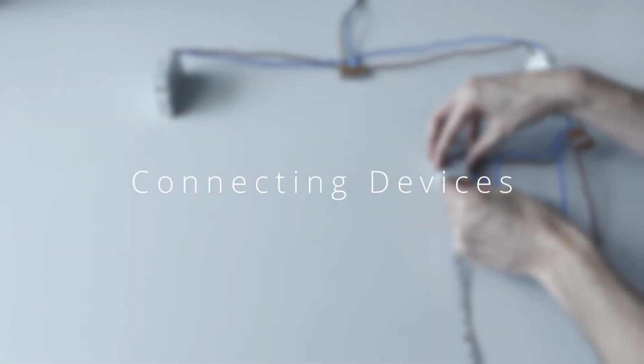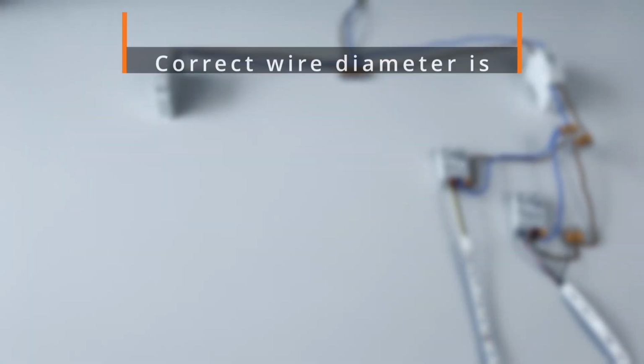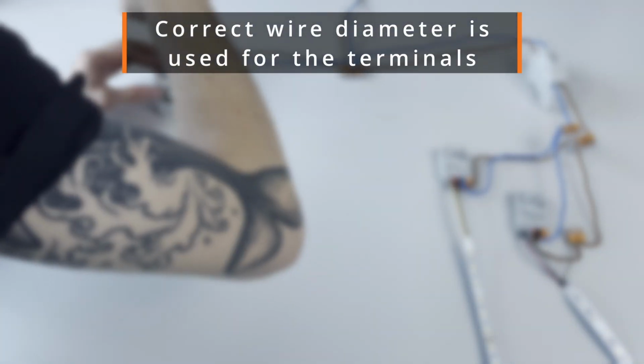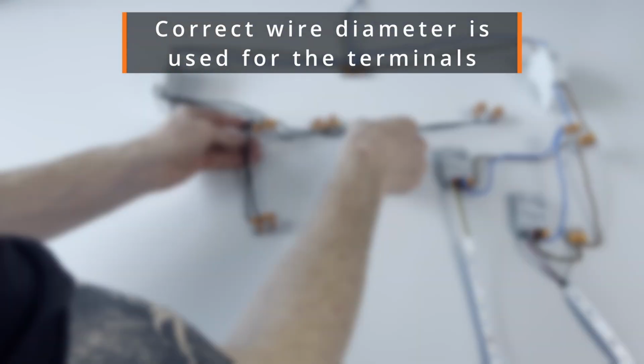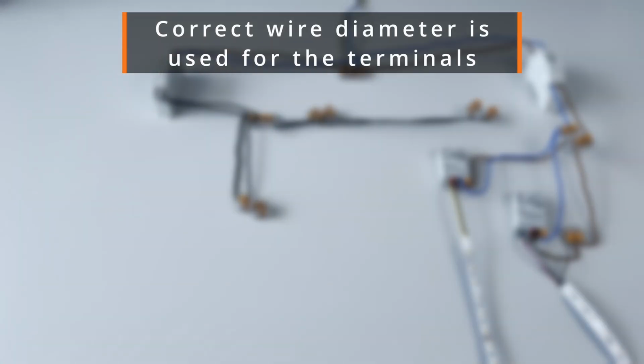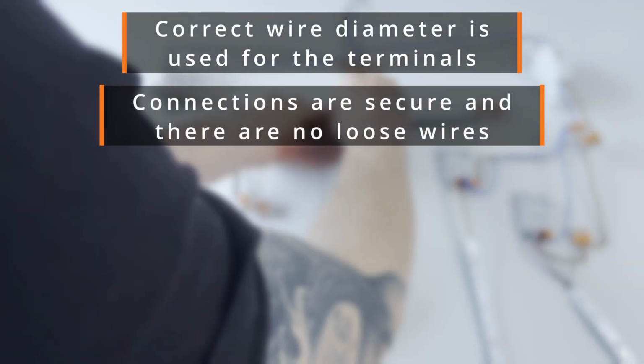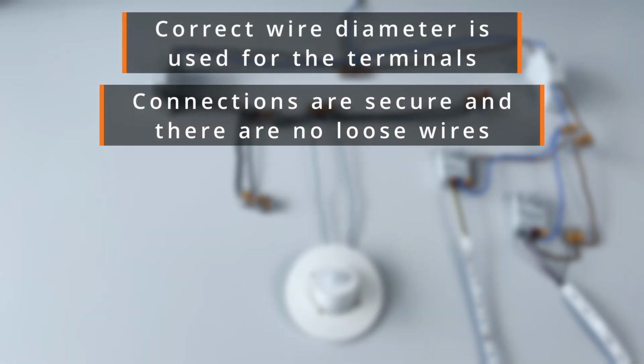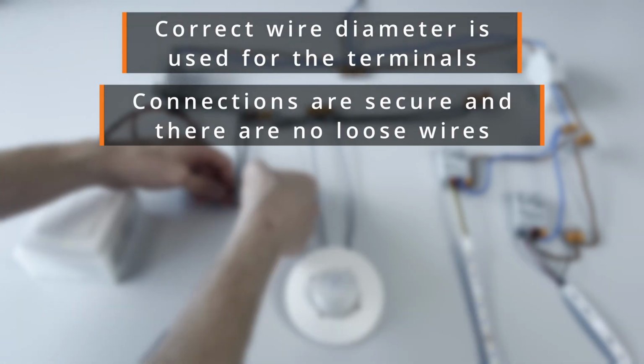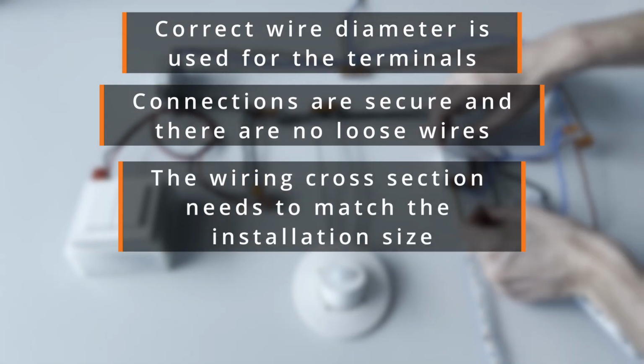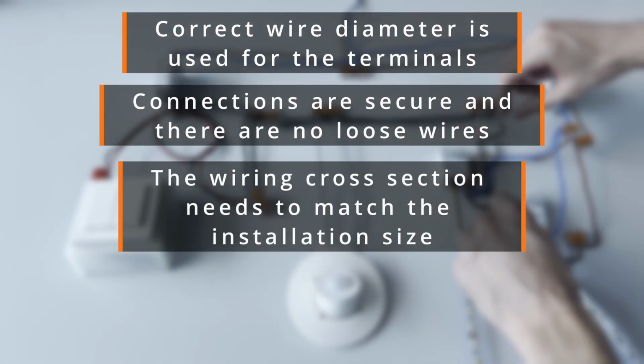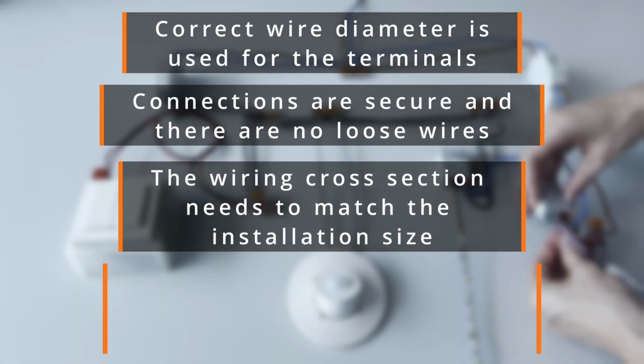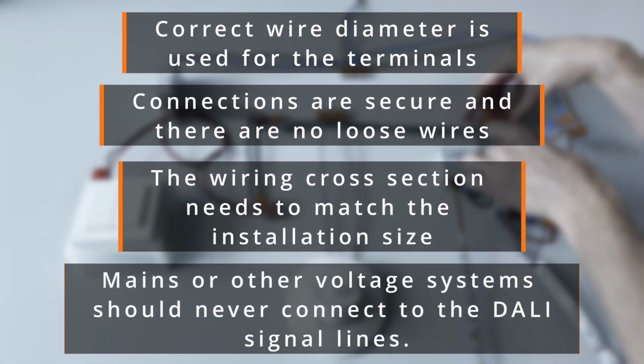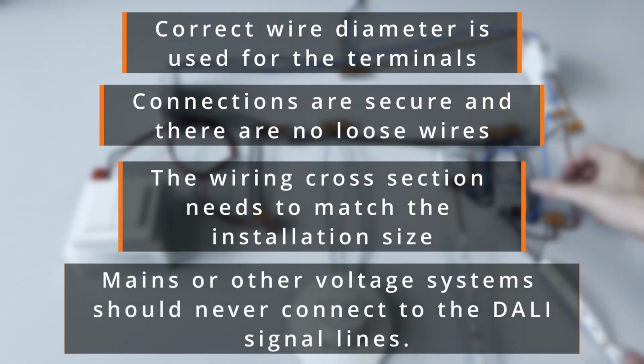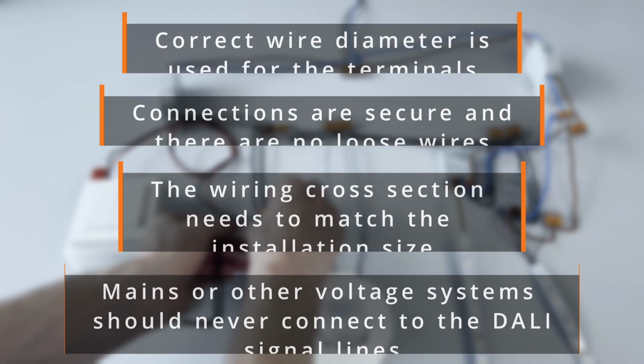Connecting devices. When wiring the devices, ensure that the correct wire diameter for the device's terminals is used as per the device's datasheet, that connections are secure and that there are no loose wires. The wiring cross-section needs to match the installation size, such that the voltage drop is not above 2 volts at maximum length. Mains or other voltage systems are never connected to the DALI signal lines.